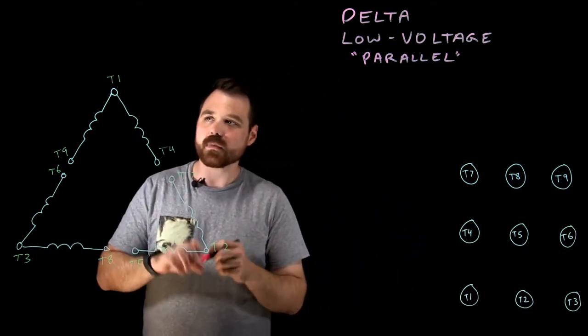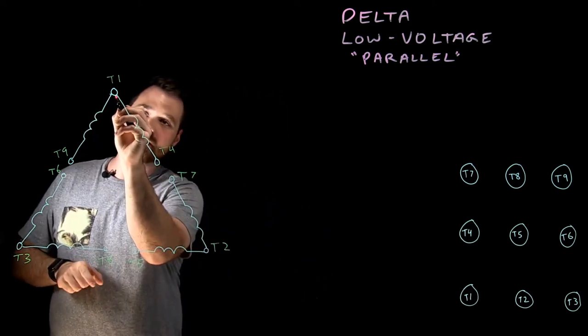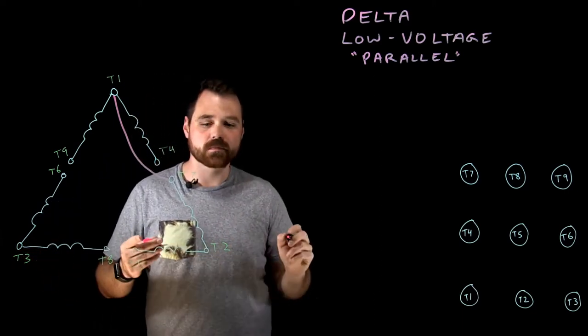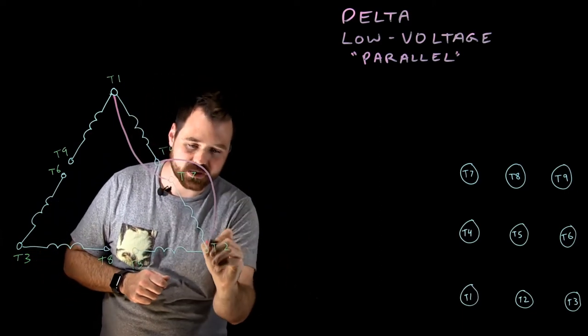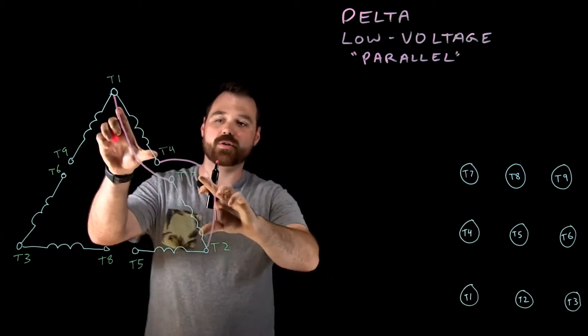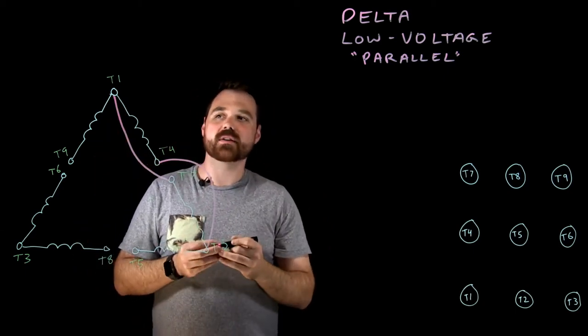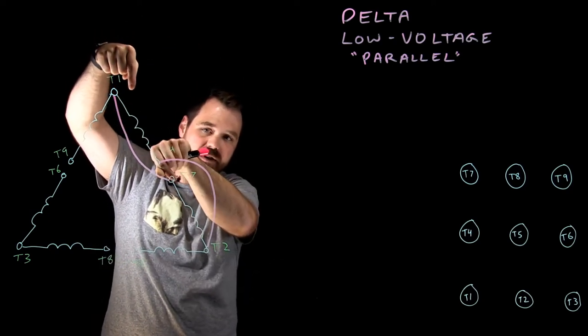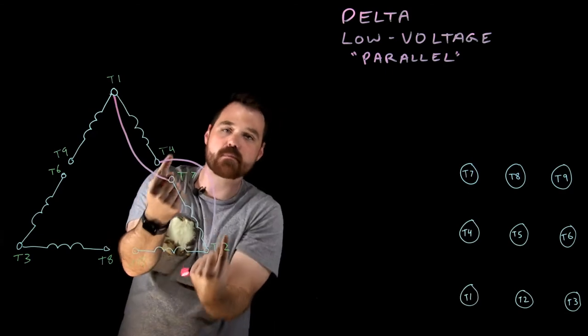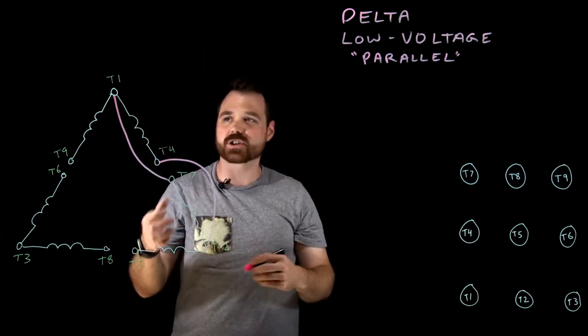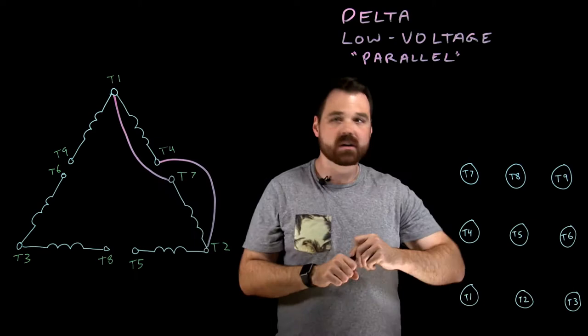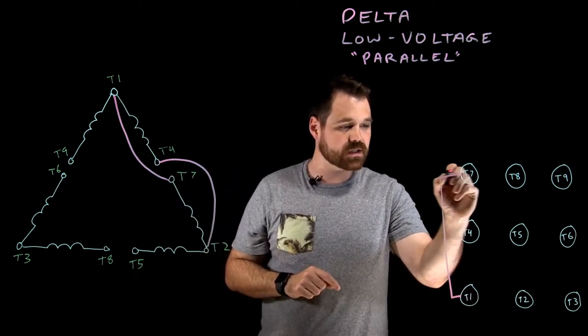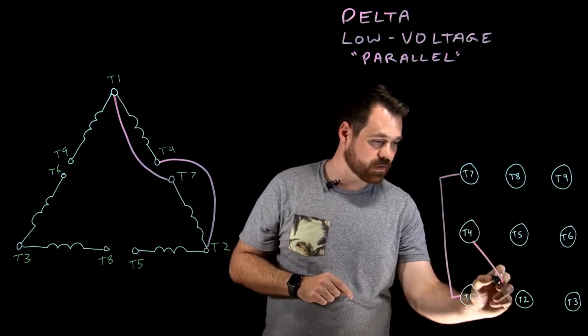We always want, in this case, T1 to be connected to T7, and T4 would be connected to T2. That would put those in parallel with each other so that if current was flowing into T1, it's now also flowing into T7 and flowing through that way and then back out. So that's our first step: T1 to T7 and T4 to T2.